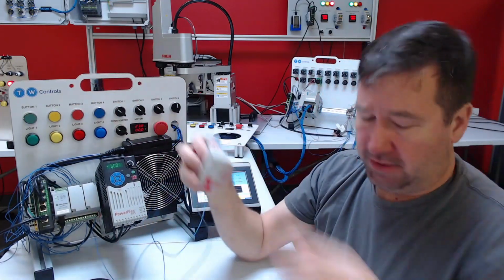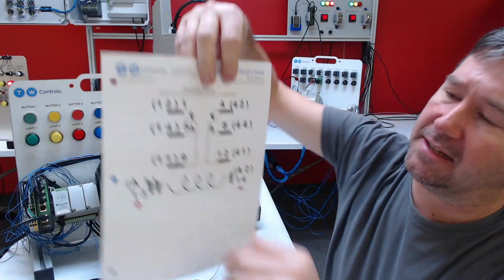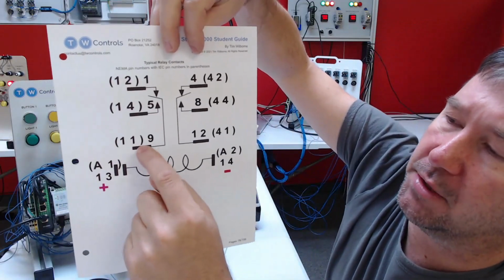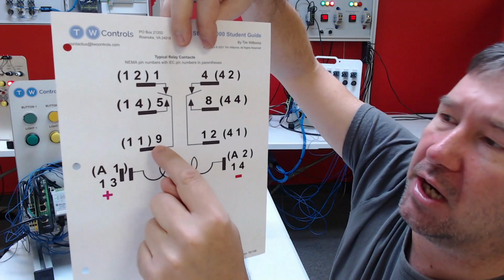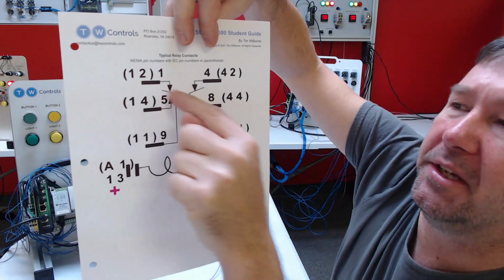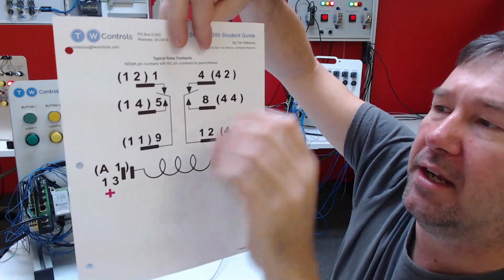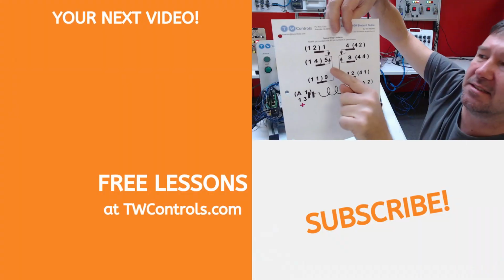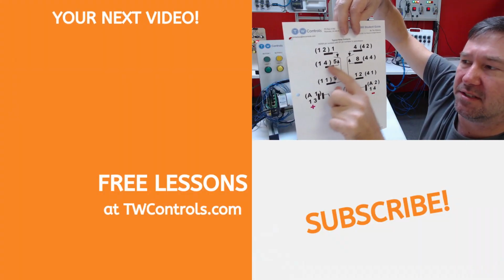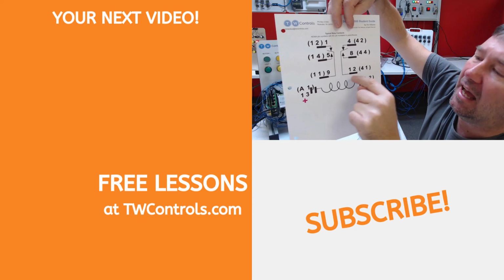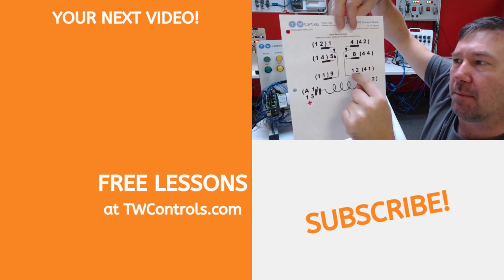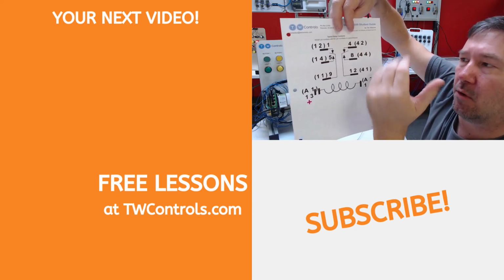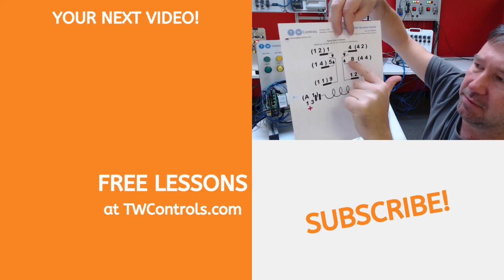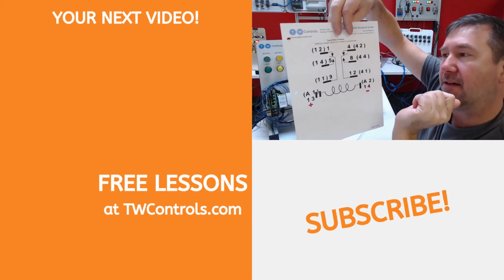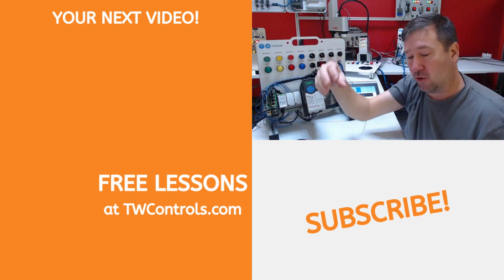And that's going to give us two nice isolated contacts. On one of them, terminal number 9 is going to be our common, and we're going to have a normally closed terminal number 1. And then when it energizes, it's going to switch it to terminal number 5. So this is our normally open contact. And on the other side, 12 is our common, and normally closed is going to be 4. We energize it, which is going to move the switch down, and 8 will be energized. So that makes 8 our normally open contact.